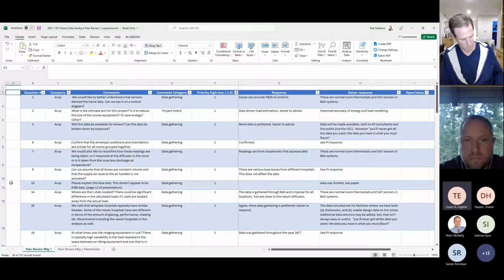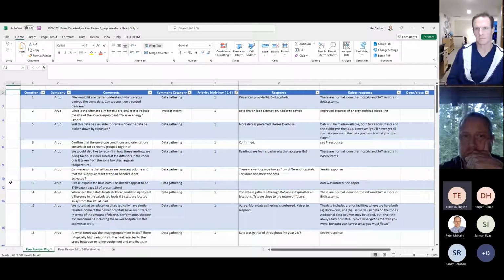I think that's where we've traditionally failed as an industry: we're very good at articulating the hottest day of the year, very good at articulating the coldest day of the year. But what we saw in South Bay is that about 70% of the year the weather outside is like 68 to 71 degrees, so the building is in neutral. Our systems are incapable of turning down -- they don't know how. What we've seen with our commissioning effort is that unless you very deliberately design systems to be able to turn down, they can't, and you run into all sorts of problems with that.